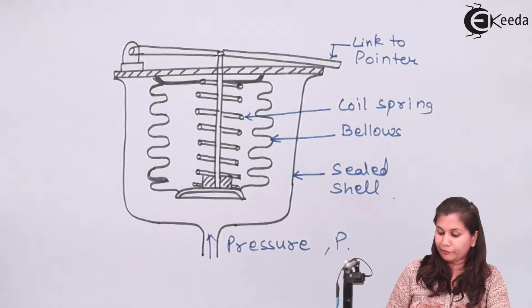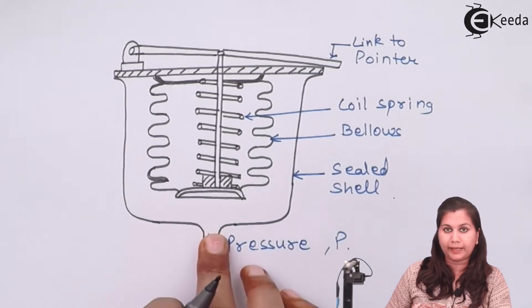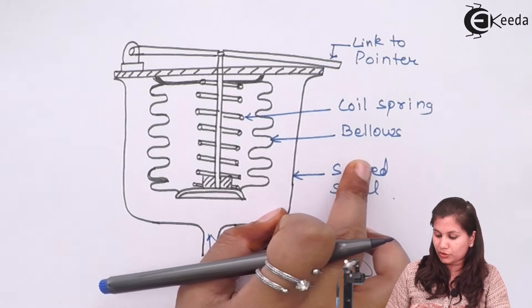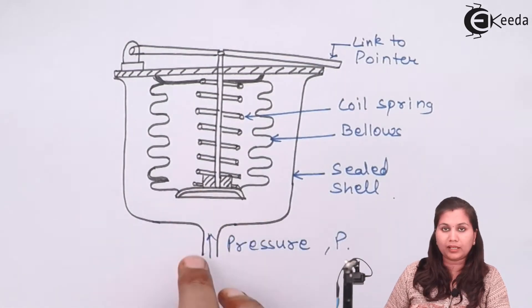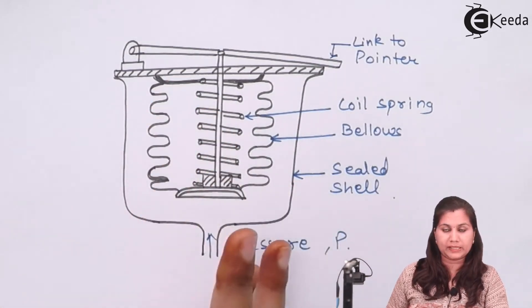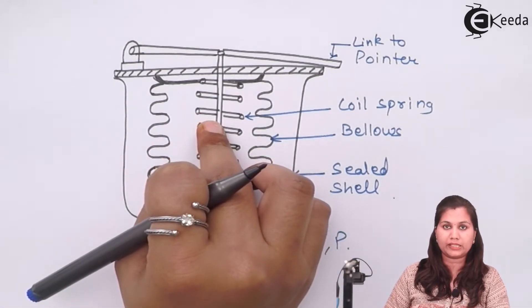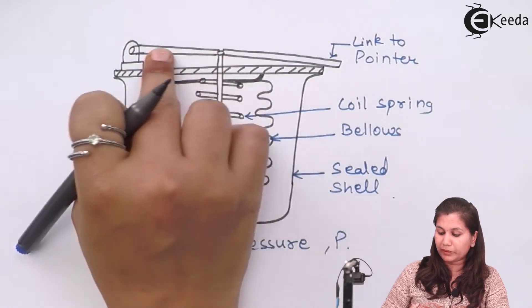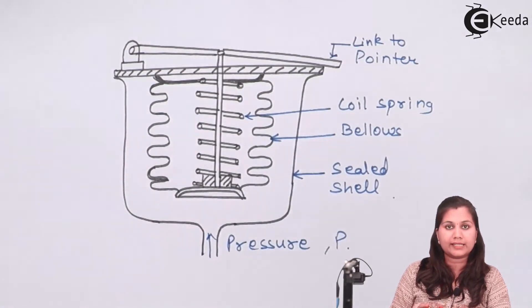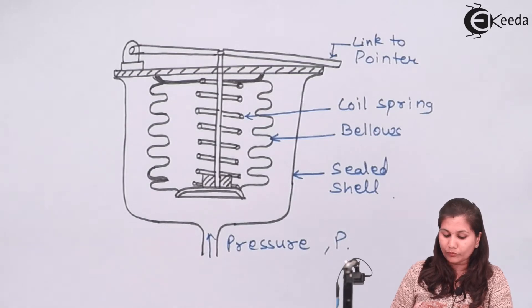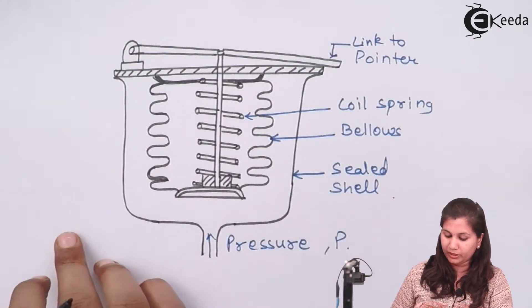This is the diagram for the spring loaded bellows. Here the pressure is applied, and in the middle you can see we are having the coil spring, and around that we are having the bellows or the corrugations. This spring in between is connected with the pointer. As soon as the pressure is applied, the bellows are going to expand, due to which the spring is also going to expand or contract, and the movement of the spring is connected with the pointer. So the pointer is going to move over the scale through which we can get the readings of the pressure. In this way the pressure is measured with the help of the spring loaded bellows.